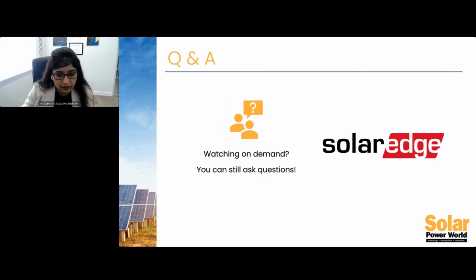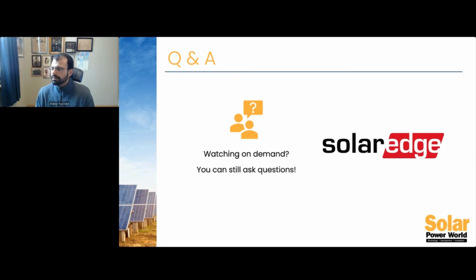Is there a requirement for the AC recombiner to be SolarEdge OEM for warranty support? The AC, no, it's not. That's a very good point. The virtual central solution that I showed you is something we created because we listened to our customers, especially with switchgear availability. However, there is no requirement to use that solution. You can buy the inverter, do the pre-wiring in your factory, and get any switchboard or any connection. There are requirements, though, that you need to have a fuse or a breaker for every single inverter, but we can get into the details during the design phase.